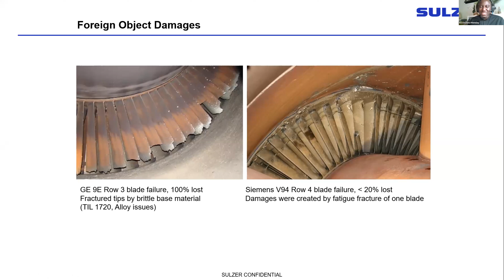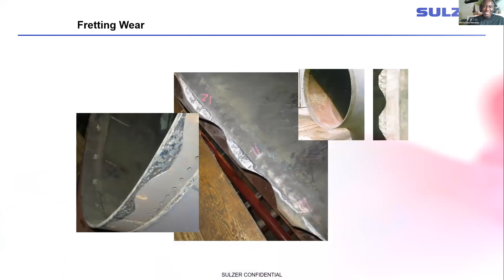They had issues with the material, so there's a technical information letter by GE that tells you at certain hours you need to do a borescope inspection of these blades, because it's a fleet issue. But if you're operating your power plant and you're not aware of this, or you don't do it, what you get is a failure.